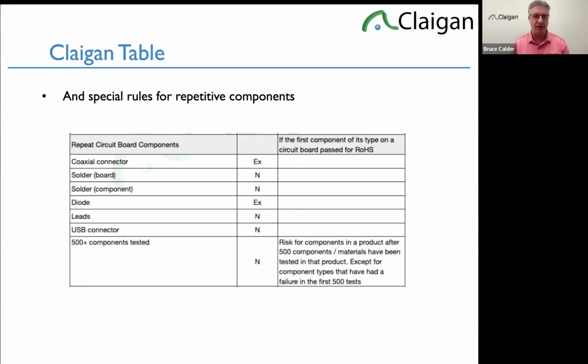Once you've tested 500 components, if we keep testing, are we going to find any new failures? No - any failure you're going to find, you've already caught, as long as you've done a good sampling plan. This is definitely for huge products, though you can do less than 500 and probably justify that too. But 500 is very comprehensive - we have big data sets saying once you get to 500, you're not going to find anything new as long as you sample properly.